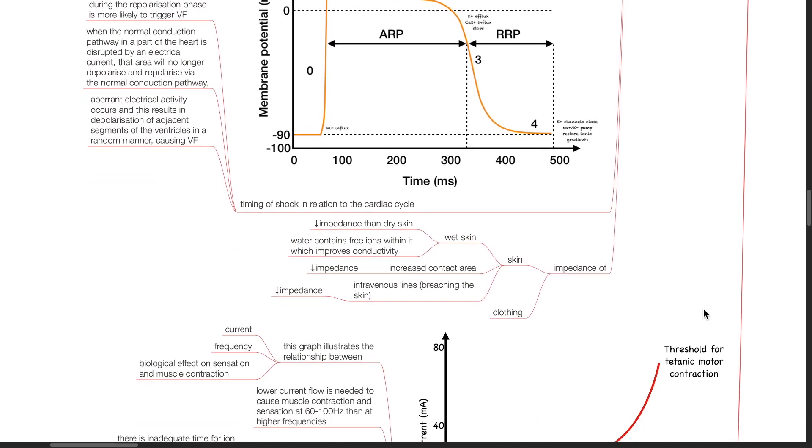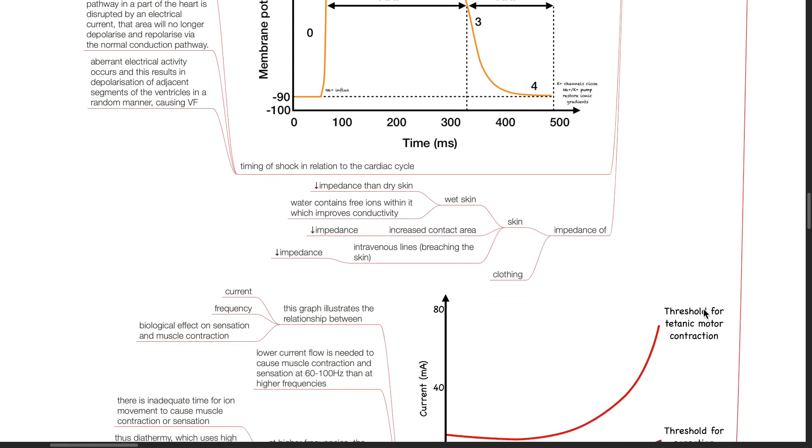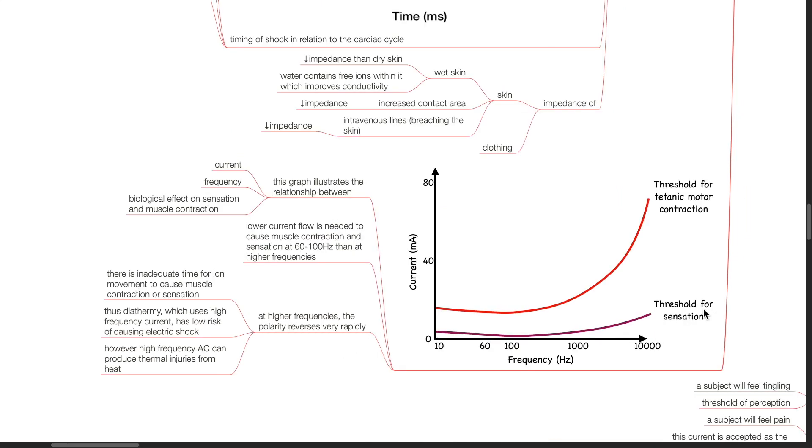Impedance of the skin and clothing. Wet skin reduces impedance compared to dry skin. Water contains free ions which improve conductivity. Increased contact area and intravenous lines which breach the skin reduce impedance to current flow. The presence of clothing increases impedance to current flow.